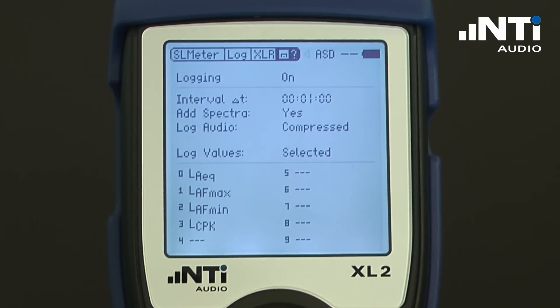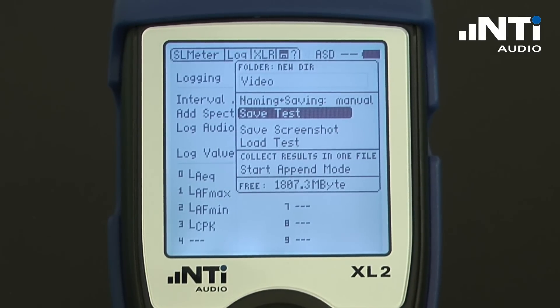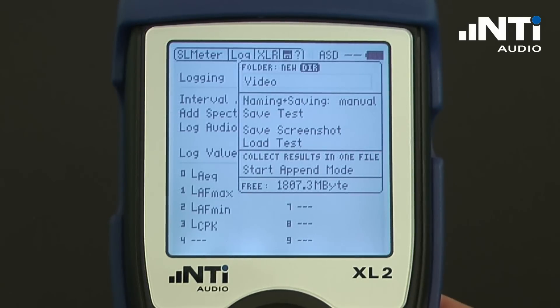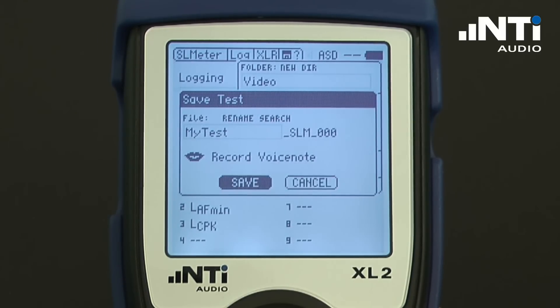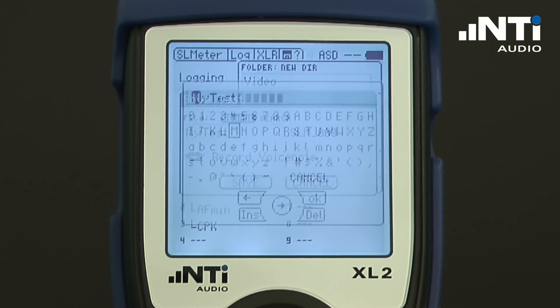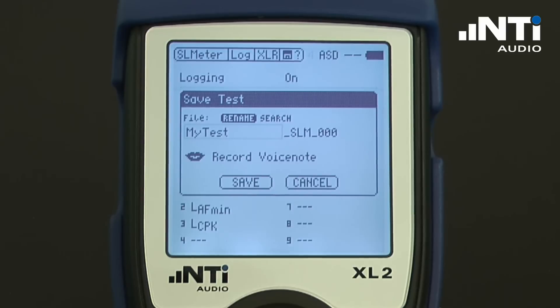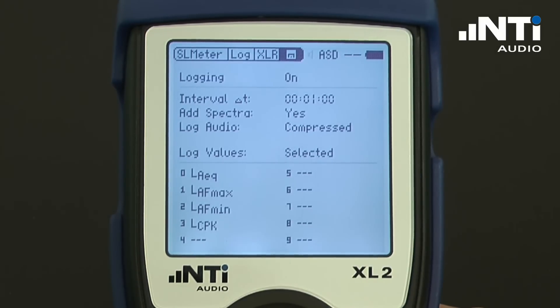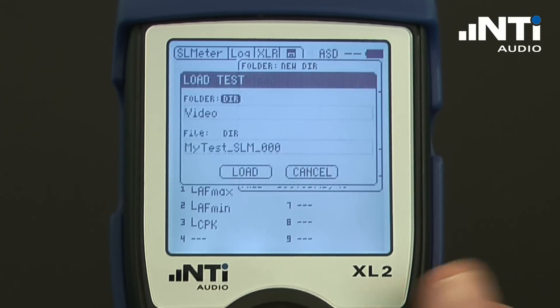At the end of the test, all the measurement results together with the test definitions, the completed report, as well as the logged results together with the compressed audio are stored. We may define the directory we are operating in to separate larger projects and handle them in individual folders. We define the test name — in this case proposed as 'my test' — which can also be renamed to any other name if desired. As soon as we press save, the complete test is stored on the SD card. We are free to change functions and do other measurements, and very importantly, we may at any time load the complete test, including all the measurement results, back to the analyzer.